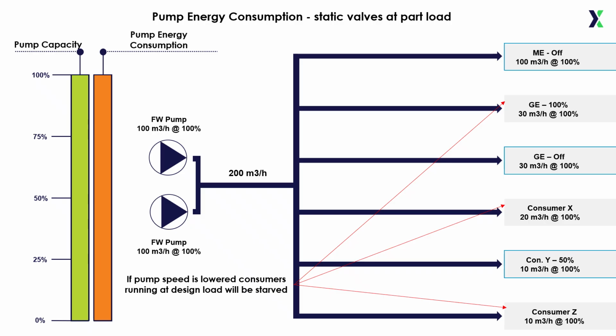However, when we examine pump energy consumption with static valves in part load condition, a critical issue becomes clear. Even though the actual demand is far below the design capacity, the pumps continue to consume disproportionately high energy, 100%. The reason behind this is that if we attempt to lower pump speed to save energy, consumers still operating at design load risk being starved of flow. This illustrates the inefficiency of static valve systems under part load conditions and emphasizes the need for smarter, dynamic flow control to align pump operation with real demand.